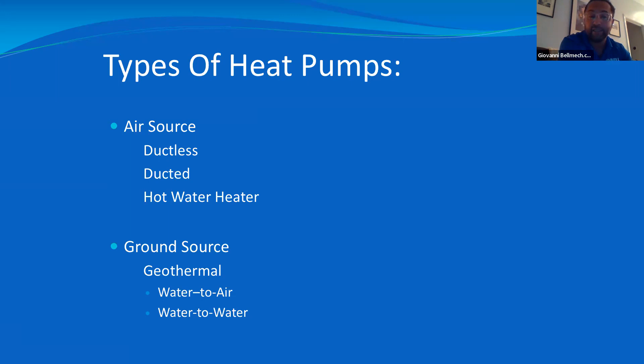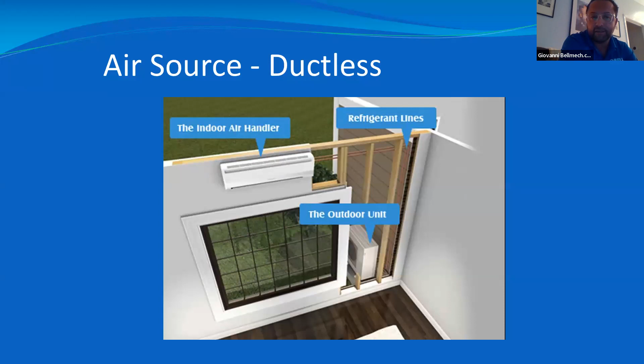Right, so this is a representation of what a ductless air source heat pump really is. You have at the bottom the outdoor unit, which is really the heat pump itself, connected to the indoor unit through, you see some copper piping there. We call those line sets or refrigerant lines. That's how the units communicate. And one of the benefits really of the ductless unit is zone temperature control. Each one of those ductless units acts as its own separate zone, so you have better control of the temperatures inside your house. If you want it cooler in your bedroom than in the living room, you can do that, therefore making it more efficient. Next slide.